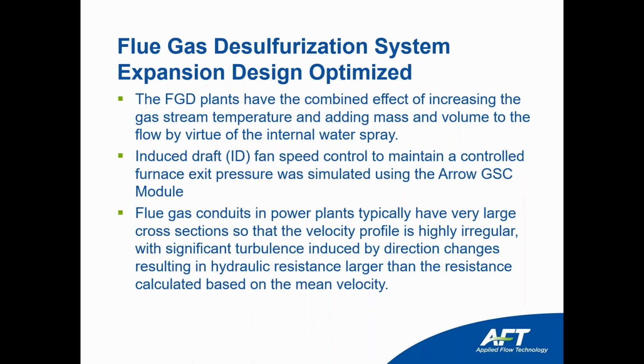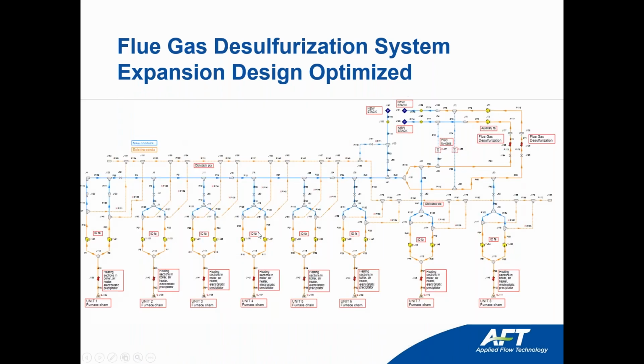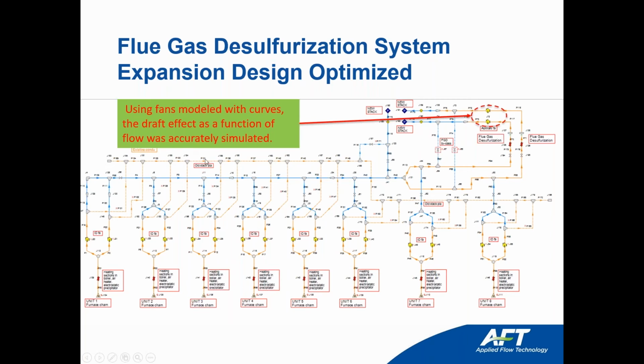Flue gas conduits in power plants typically have very large cross sections, so the velocity profile is highly irregular, with significant turbulence induced by direction changes, resulting in hydraulic resistance larger than the resistance calculated based on the mean velocity.